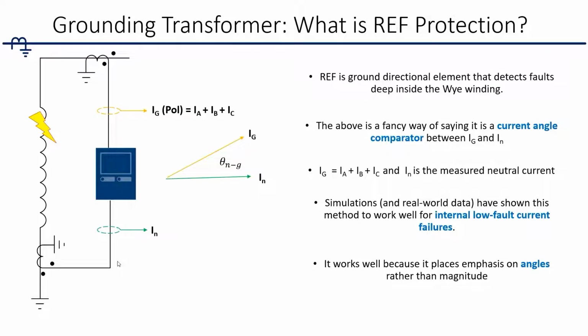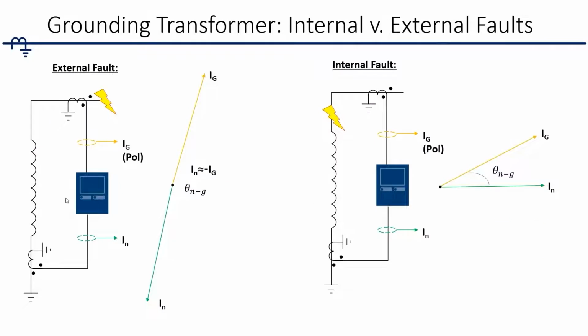Overcurrent coordination and overcurrent elements work great for utilities because there's so much fault current availability. With inverters, not so much. It just doesn't seem to work real well. There are other items like voltage restrained overcurrent that you can use, and those do work well. There are times when they don't work so well, but this works well because of the angle comparator. So it's operating on angle rather than magnitude.